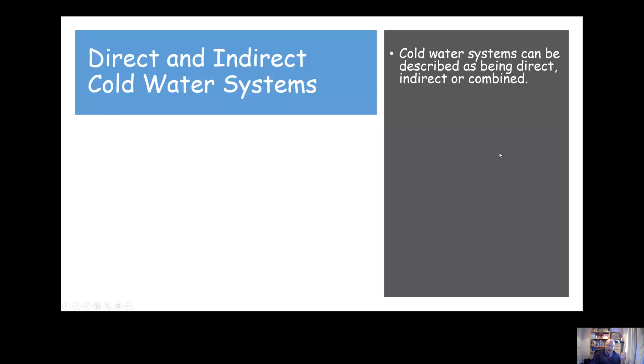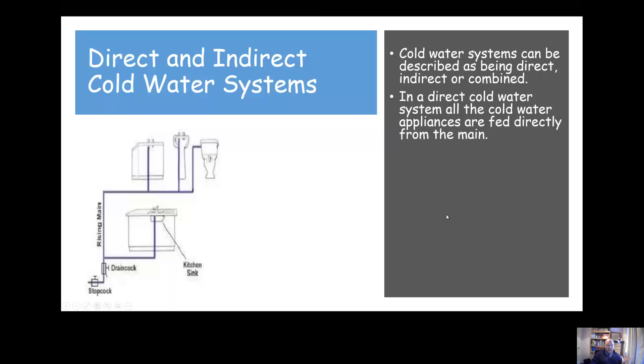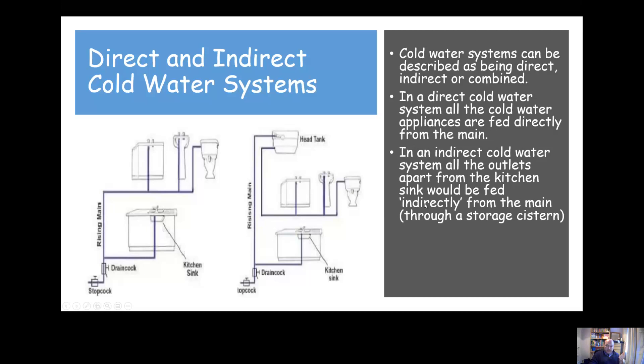Cold water systems can be described as being either direct, indirect, or combined. In a direct cold water system, all of the cold water appliances are fed directly from the mains — that pipe would be described as the supply pipe because it's coming straight from the mains. In an indirect cold water system, all the outlets apart from the kitchen sink would be fed indirectly from the mains.